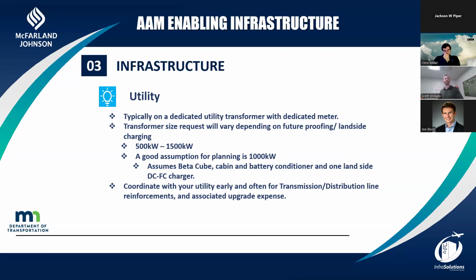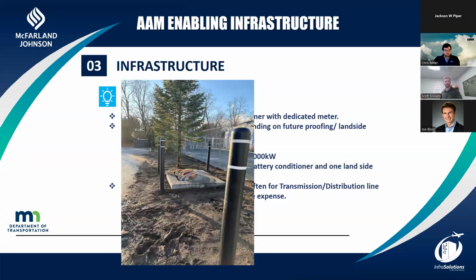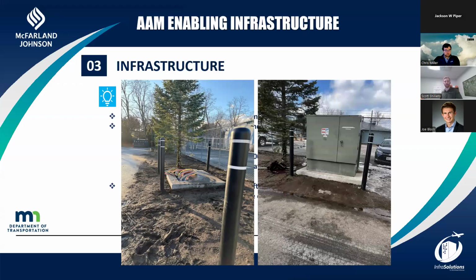Coordinate with your utility early and often, though. Utilities all like to deal with real numbers, and they may not provide you any information if reinforcements are required until you submit that utility request. So I recommend getting that in early and coordinating with them as soon as you can, because what you don't want to happen is them coming back and saying, hey, we need to reinforce this area, it's going to be 700,000. That could kill a project pretty quickly. So get that in and get that coordinated as soon as you can, and it avoids going from this to this a lot quicker.